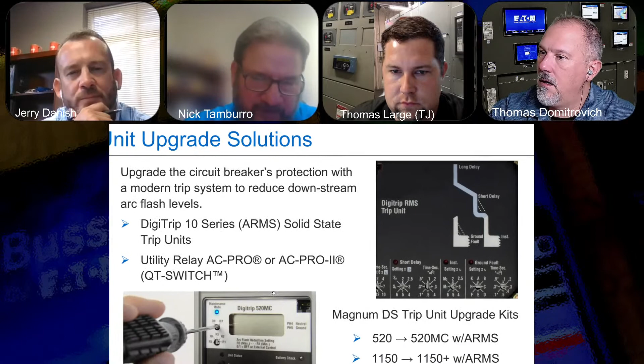The more serious engineers, not the tech center, incorporate it into their trip unit, so it's right there. We recognized that we'd have customers wanting arc flash reduction on their trip units, and there would be a rush on the 520. The only two with ARMS built in are the 520 MC and the 1150. So we made kits to go from a 520 to a 520 MC with ARMS, and from 1150 without ARMS to 1150 with ARMS, and we still carry those kits today.